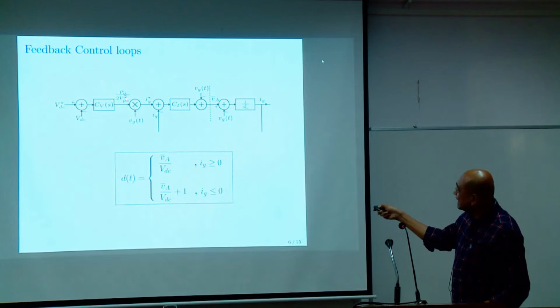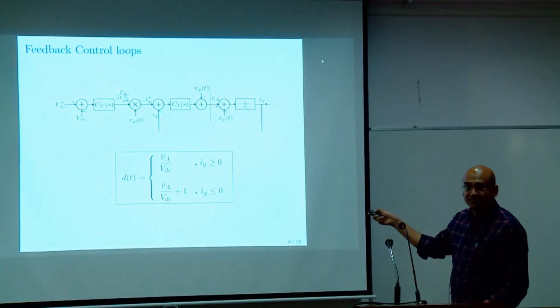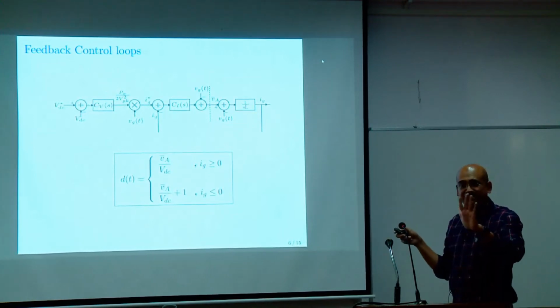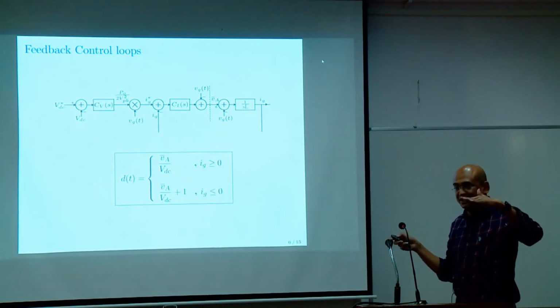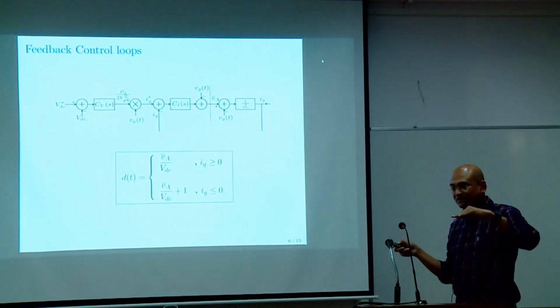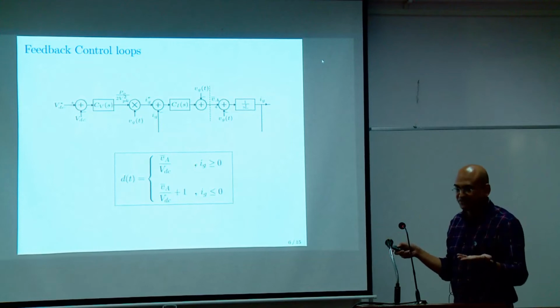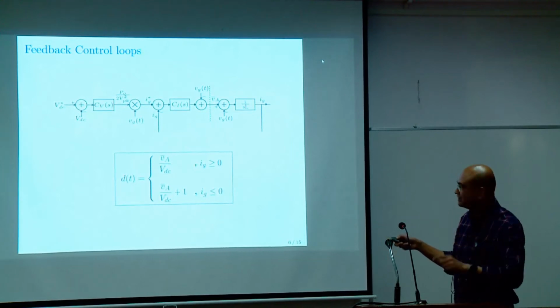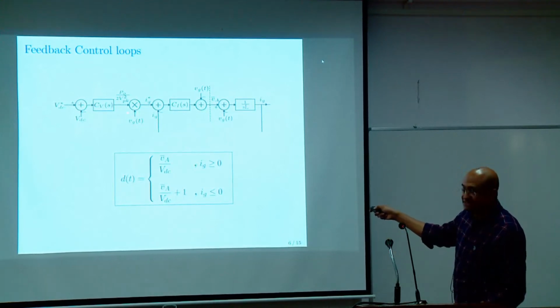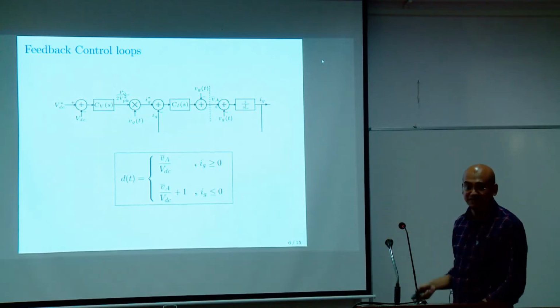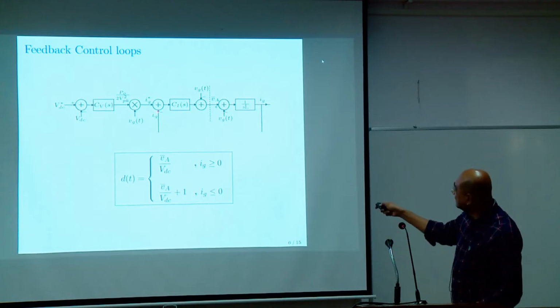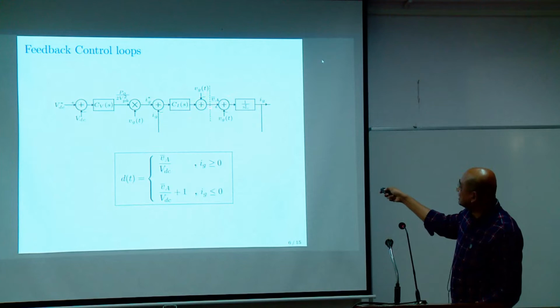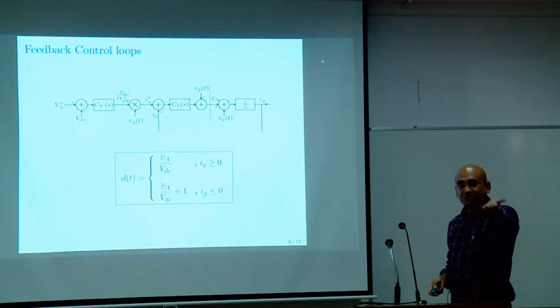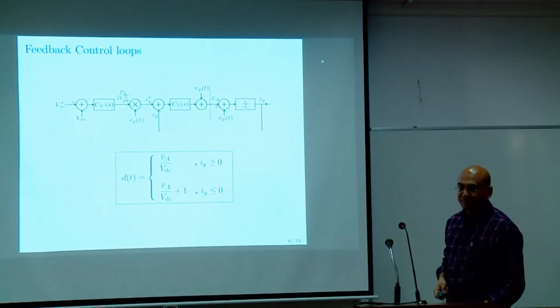Here I am dividing it by 2 Vp square, but in actual implementation it is not required. Closed loop control will understand, and instead of giving you PO, it will give you PO by 2 Vp square - that is the closed loop control. And then you multiply with Vg, then you will get the current reference, the grid current reference, and then the inner current controller will tell you what should be the voltage that you should apply to make that current like that, correct?